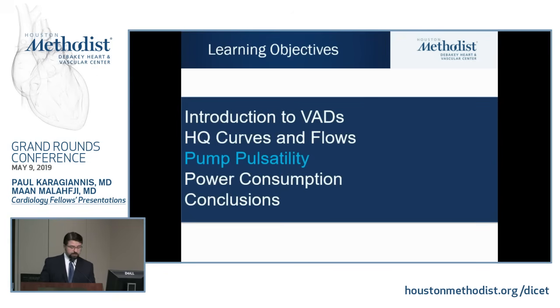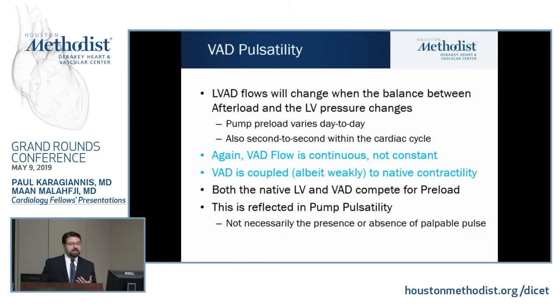I want to address pump pulsatility really quickly as well. This is another fundamental concept, and it also is informed by the HQ curve. We talked a few minutes ago about how LVAD flows are determined by the pressure differential, the pump afterload, and pump preload, and this may vary to a degree day to day with a magnitude that we're familiar with.